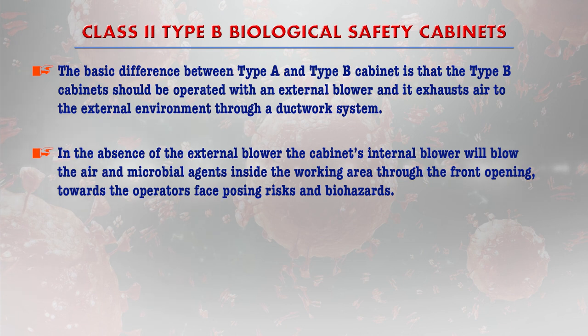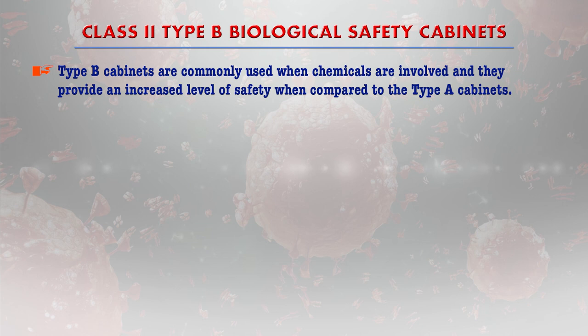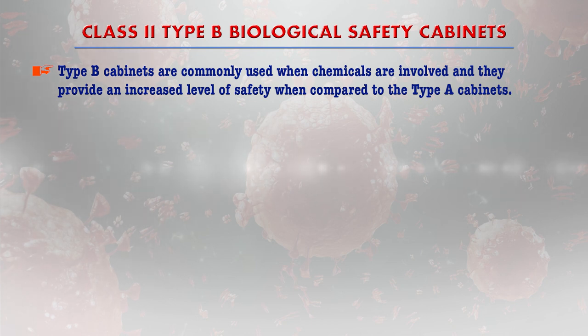In the absence of external blowers, the cabinet's internal blower will blow air and microbial agents inside the working area through the front opening towards the operator's face, posing risk and biohazards. Type B cabinets are commonly used when chemicals are involved in experiments and provide an increased level of safety compared to type A cabinets. Different biohazard levels call for different types of cabinets.